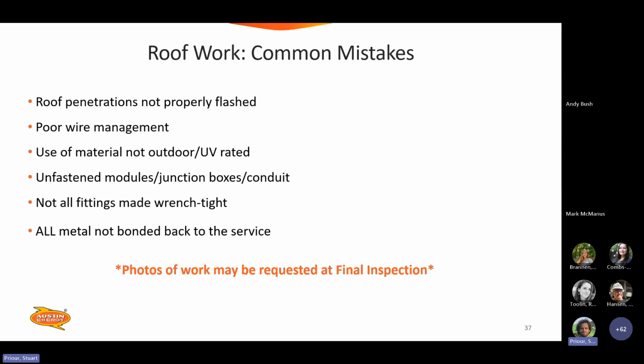And all metal is not bonded back to the service. Any metal component that is likely to become energized, as we know, NEC says has to be bonded back to the service for the functioning of all overcurrent and trip devices. And we might require photos of your work at the final inspection, so be sure to have those. And that's under the array, that's inside junction boxes. That's any part of the project on the roof that we couldn't see from the ground.